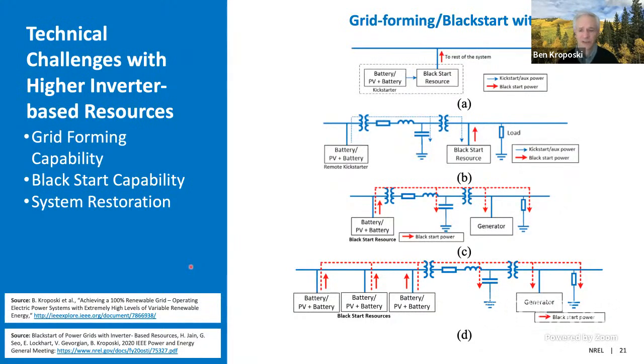Other technical challenges include the ability to black start the grid. So one of the things that happens now, right, if we take the grid offline, we need resources that are capable of forming their own grid, black starting from that blackout condition, and then going back in a sequence and doing a complete system restoration. So we know how to do that for large-scale grids with synchronous generators involved. There's a number of resources that are identified as the black start units that will help us bring the grid back online. But if we have lots of inverter-based resources, how do we do that similar type of a system? And we know it's possible. We've done it on small scales, but it's definitely a key component when we think about running grids with large amounts of inverter-based resources.